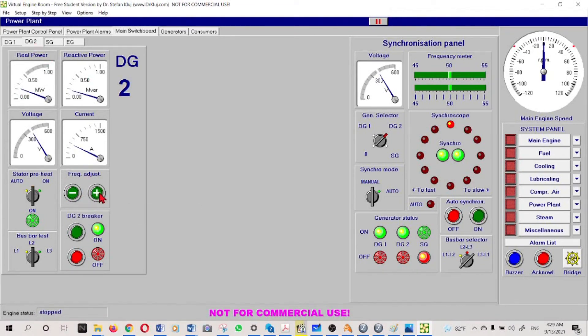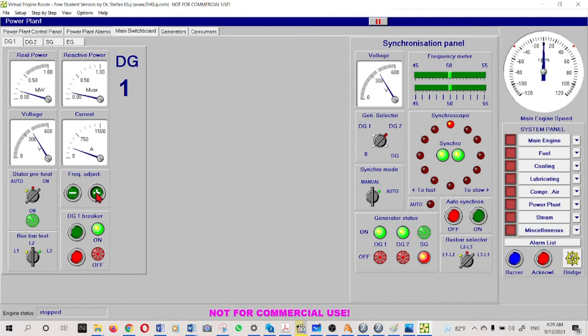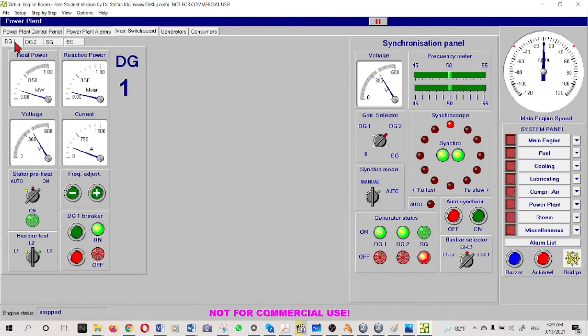If I want to decrease - now it is number one generator - I can reduce the load by adjusting its frequency speed. Now we can see that we have done the sharing of generators. They are sharing kilowatts - roughly the same kilowatts - and the reactive power is also being shared between the two generators.